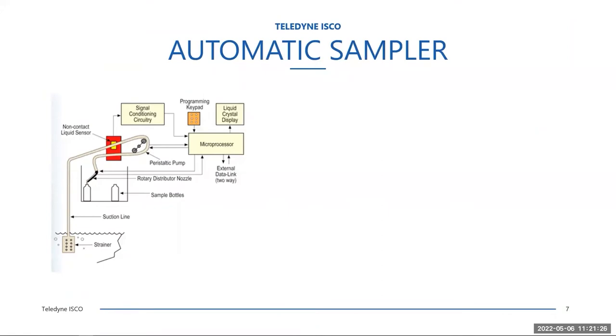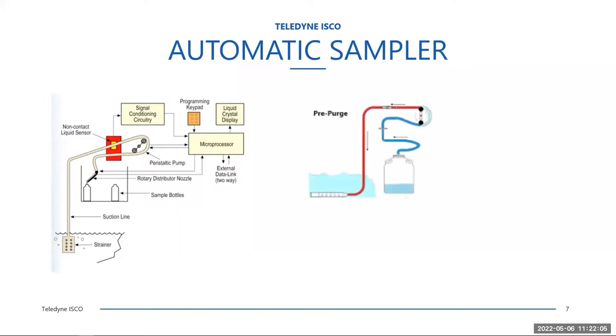An automated sampler consists of several components. You'll have a controller unit with a microprocessor, program memory, and operational software that the user defines to control how the sampler operates. Most samplers will have a display so you can evaluate the current status of the sampler. There will be a pump that, based upon how the user has programmed the unit, will operate and collect the sample. Initially, the pump will run in reverse to purge the line and remove any residual fluid that may have migrated up in the line since the last sample event.